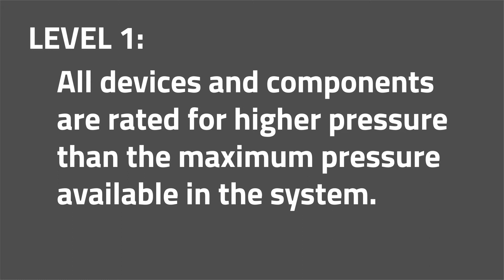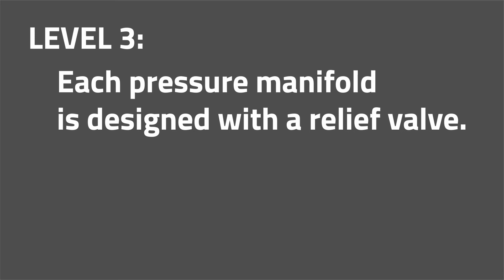We've designed it in such a way to use 3 levels of safety to keep the coil from overpressurizing. The first is to use devices that are rated for a pressure higher than the maximum pressure available in the system. The second level of safety is we set limits inside the software and the PLC and the safety controller as well. The third level of safety is we have a relief valve on each pressure manifold. So if we do end up having an overrun condition, the relief valve will exhaust any pressure above the set level in the relief valve.